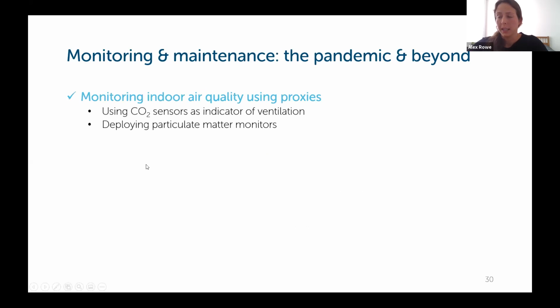the customer decided to use those CO2 sensors that they replaced as an indicator of ventilation. And they are actually thinking about deploying some particulate matter sensors or monitors in order to determine if their HVAC filters that they upgraded to MERV 13 are removing particles from the airstream as intended.